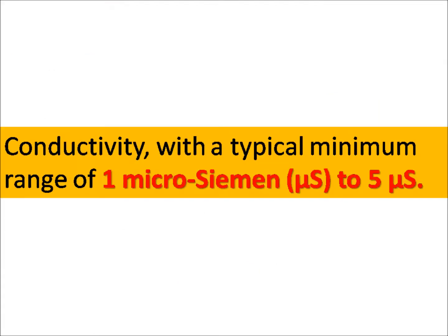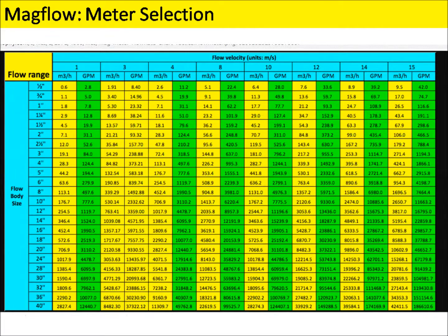From the theory you came to know that magflow works on conductivity of fluid. Minimum conductivity should be 1 microsiemens to 5 microsiemens. From this table you can select flow meter size versus velocity. You can select a magmeter according to velocity.